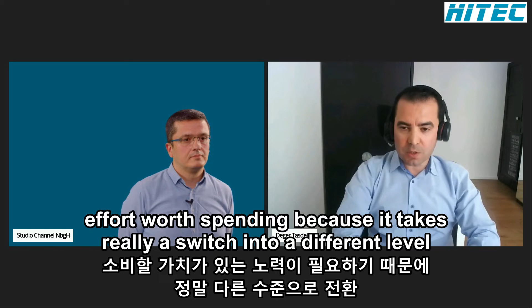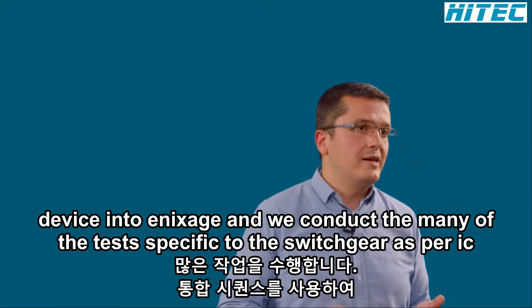Sure. First, for the development of the device itself, we had separate testing sessions, type tests for the standalone device. And when we succeeded in this, our first integration was in NX Air, up to 17.5 kV and 50 kA. Therefore, we integrated the device into NX Air, and we conducted many of the tests specific to the switchgear as per IEC, also with an integrated SIQuench. And there, we have proved the performance of the device in parallel.